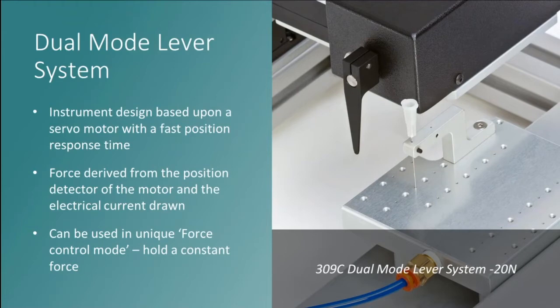The electronics which control the instrument have another mode where we are controlling the tensile load of the sample. We might call this an isotonic condition - it's basically a force control mode. This allows us instead to measure the profile of the tendon shortening based upon a loading profile that is user defined. We can input this profile to the instrument in the form of a command signal, an external voltage, rather than driving a length change to try to mimic some sort of load curve.